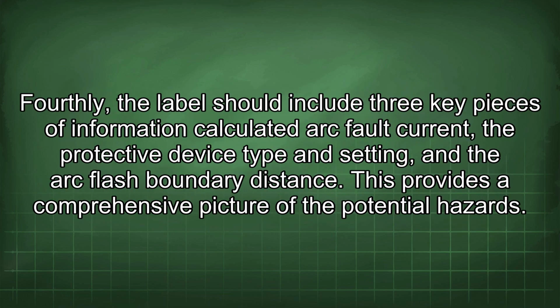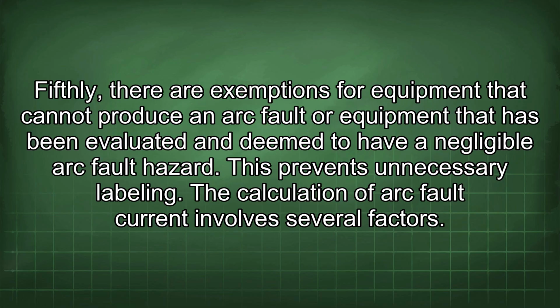Fourthly, the label should include three key pieces of information: calculated arc fault current, the protective device type and setting, and the arc flash boundary distance. This provides a comprehensive picture of the potential hazards. Fifthly, there are exemptions for equipment that cannot produce an arc fault or equipment that has been evaluated and deemed to have a negligible arc fault hazard. This prevents unnecessary labeling. The calculation of arc fault current involves several factors.